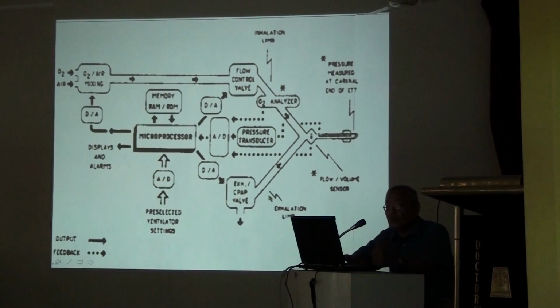So you have to have a thumb on this outlet. If you close this outlet, then only the lung will open. If you remove your thumb, again the lung will deflate. So in tandem, once this is open, in the next phase there is simultaneous closing of this, opening of this valve and closing of this valve. These two things operate any ventilator in the world. If you look at any ventilator, these two are the basic valves which control the machine, the entire mechanism. So this is very easy for you now. Now comes sophistication.